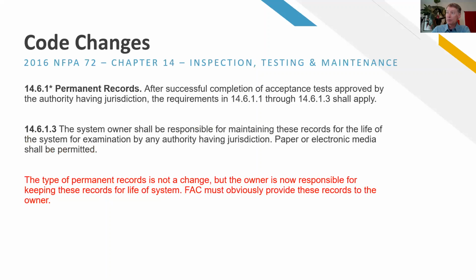Permanent records? Yep. Okay. So your fire alarm contractor is going to do an inspection. They're going to do an annual test of the system, and the records for the acceptance test, which is when the system is brand new, have to be maintained for the life of the system, and they put that on the owner. So just make sure you're keeping your documentation in a safe place. Any good fire contractor should hang on to these after a while. I know that I've sent plenty of inspection reports to more than one person more than once, but if you ever need it, we'll have it too. But the ultimate responsibility for archiving inspection reports does rest with the owner.